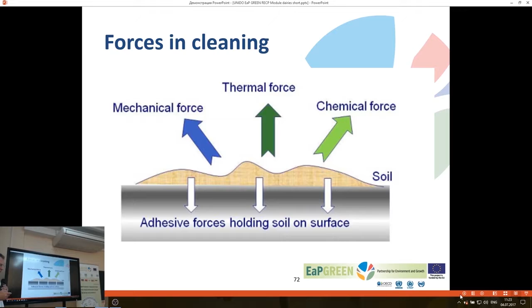Now, regarding chemicals, regarding parameters for cleaning in place plants. Mechanical force also means velocity of cleaning agent, velocity of the water, velocity of alkaline solution, and so on. This should be in the range of 1.5 meters per second. So it's actually quite fast circulation. Caustic concentration, usually optimum, is between 0.5 to 2%.